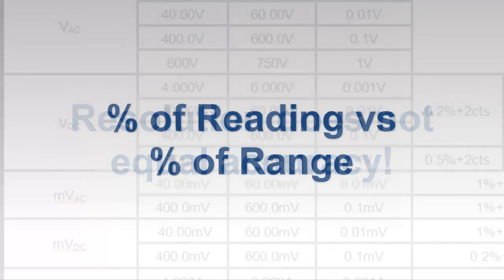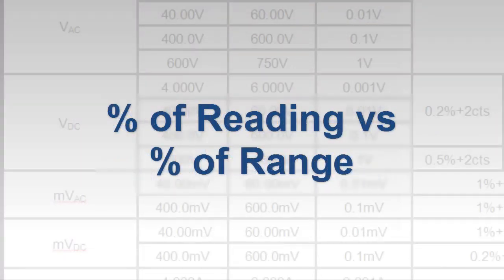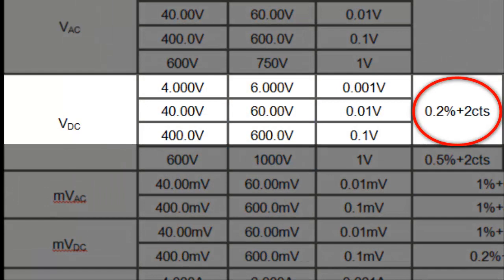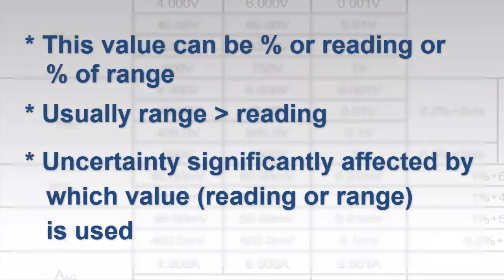A second factor in calculating uncertainty is expressed as a percentage. Recall our previous example specification of plus or minus 0.2% plus two counts. This indicates that the total uncertainty is two counts plus a percentage of a value. This can be a percentage of the reading or a percentage of the instrument's range. Uncertainty can be significantly affected by which of these values—reading or range—is used in the calculation, since the reading is generally much smaller than the range.